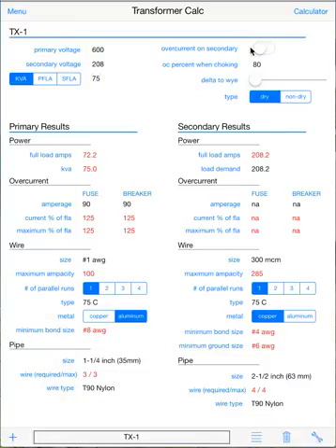Over here you can turn secondary fusing on if you so desire. So if you're going to have overcurrent protection on your primary and secondary, you can turn this on. It will seriously affect your maximum percentages on your primary especially. I'll put it on right now and you'll see that now that you have secondary fusing, you can put your primary fusing up to 300% in this scenario. Let's turn it back off.